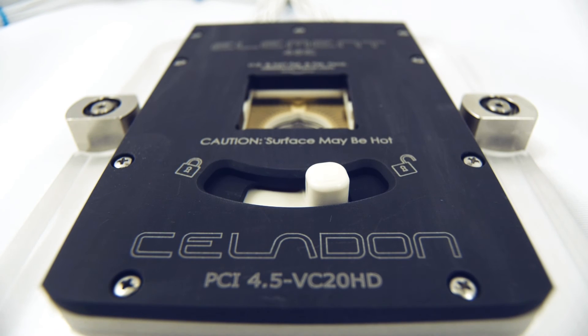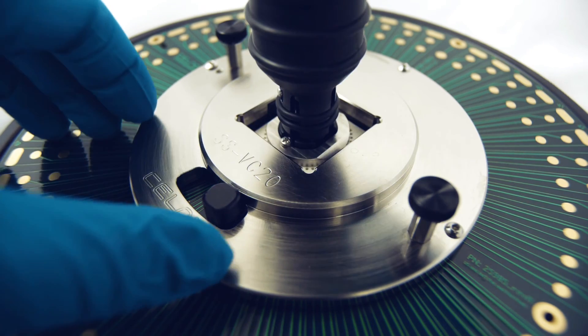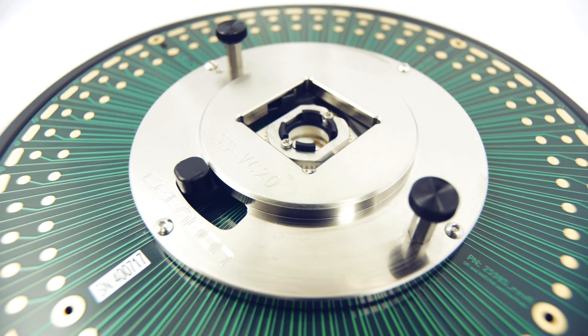You can quickly change probe cards for different wafer layouts, pad array orientation, or when probe cards are ready for cleaning, and you don't need to take the interface out of the tester, reducing triboelectric interference or interconnect issues.